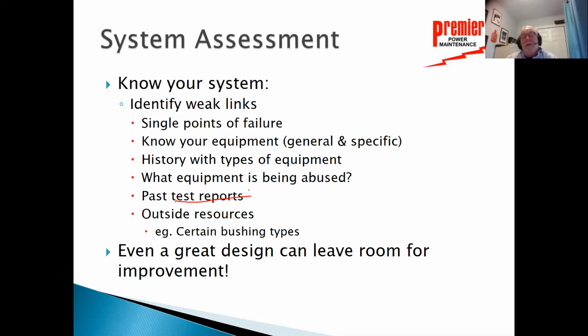It may meet the existing standard, but if the past test report looked a lot better than what we've got right now, we need to notice that the equipment is deteriorating, even though it's still acceptable for service. So that's something that a lot of people overlook. We just got a good test, it looks good, that's okay, but how is it now compared to what it was? I can relate to that as being a 68-year-old going to the doctor. The doctor says everything's good. It's like, well, it may be good, but it's not what it was 40 years ago. So there's a deteriorating process there.